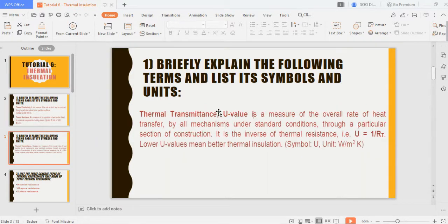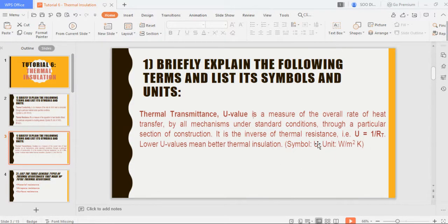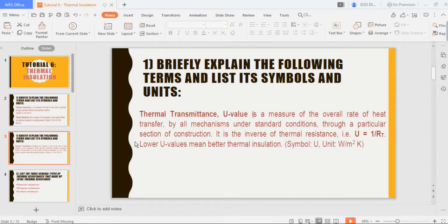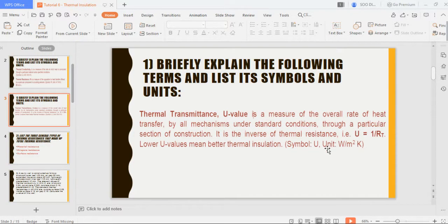Thermal transmittance, which is the U-value, is a measure of the overall rate of heat transfer by all mechanisms under standard conditions through a particular section of construction. It is the inverse of thermal resistance, so U equals 1 over R. A lower U-value means better thermal insulation.